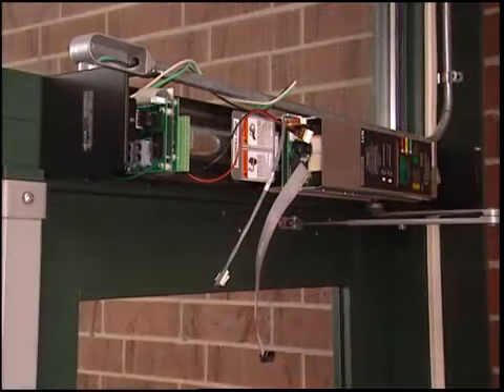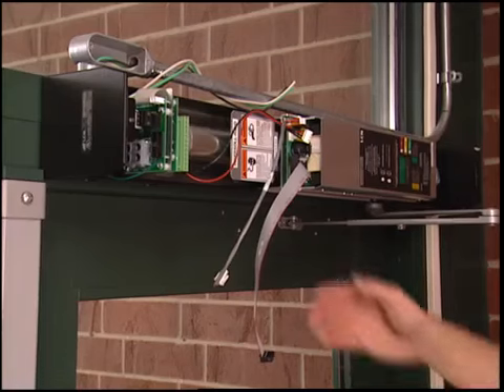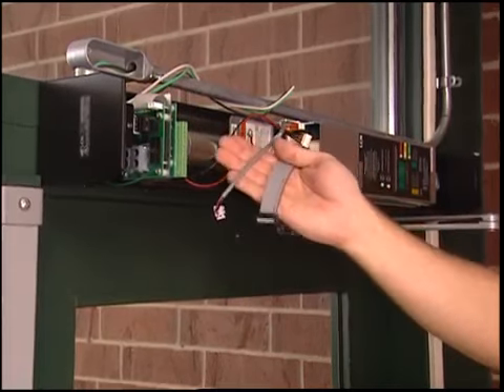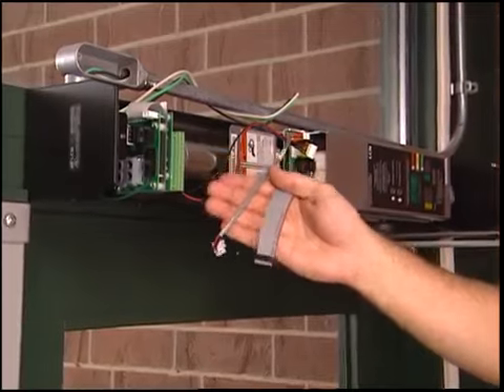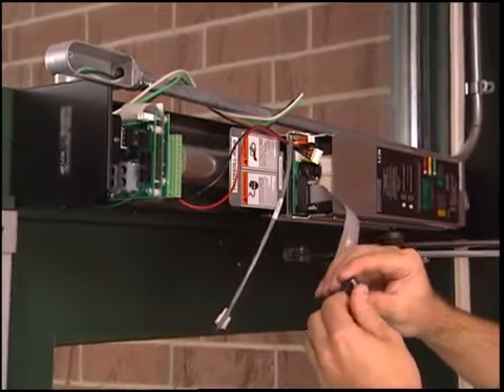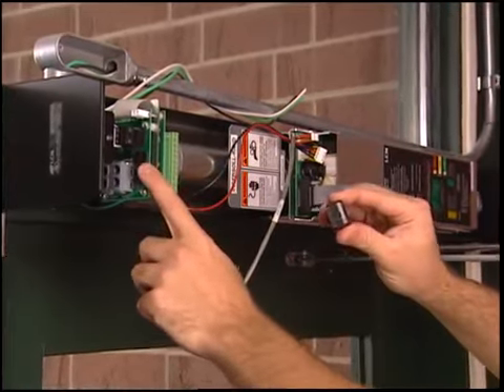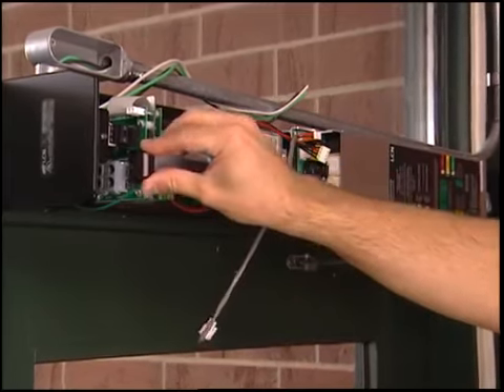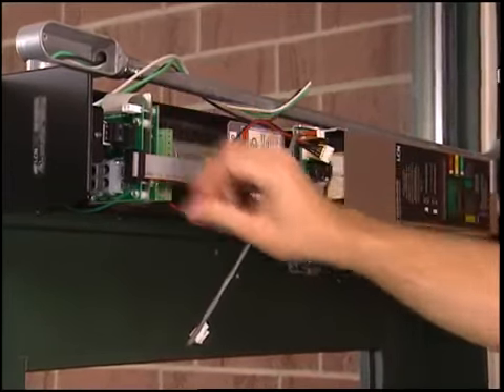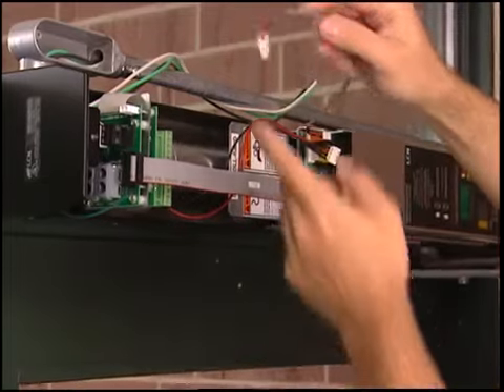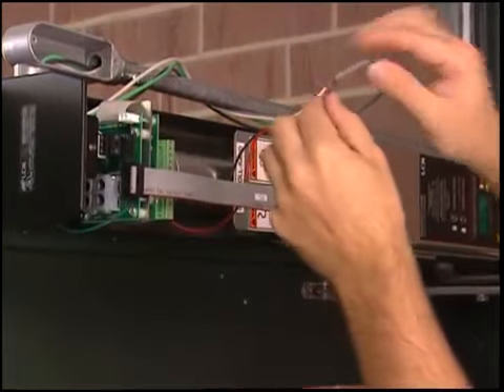Now, it's time to wire the control box. Attached to the control box, you'll find 2 color-keyed wire harnesses. The first is a ribbon cable connector. Attach the loose end of the ribbon cable to the rear board assembly, sometimes referred to as the I/O board. The second connector is a 2-wire lead for the 120-volt AC power.